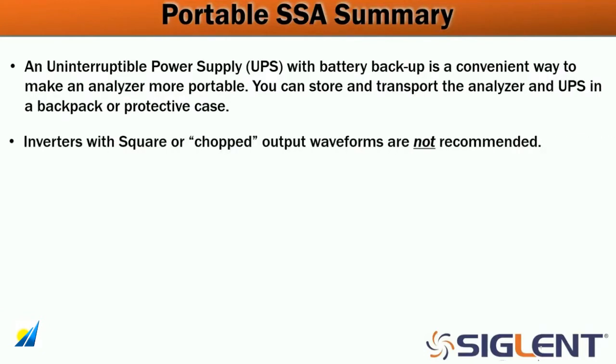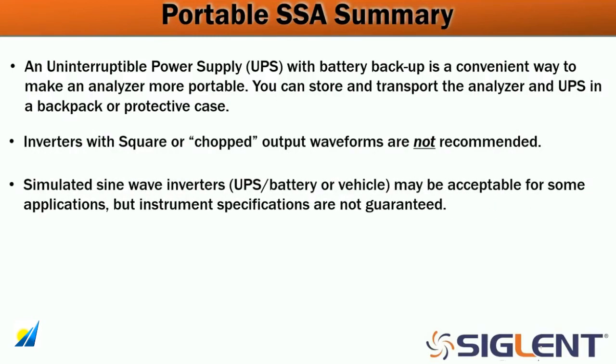And so to summarize the remote-powered SSA application: an uninterruptible power supply with battery backup is convenient and usable. Stay away from chopped waveforms or chopped outputs. A simulated sine wave is acceptable, but a true sine wave is going to be better. And to ensure accuracy, we recommend comparing data from mains-powered measurements along with data collected in your remote or portable power application. The more data you collect and the more comparisons you get, the more comfortable you're going to be with the data that you have.